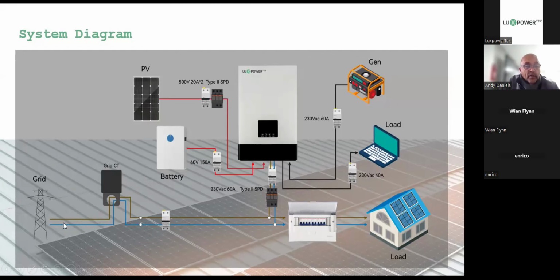So it'll be on the positive, on the live incoming before the main breaker. There is an arrow on the CT which shows the direction of flow of current, right? So it's always from the grid to the load. That's how it should be installed. And if you do make a mistake with that, you can always reverse on the maintenance page. We do give you an option to reverse the direction of the CT if you've installed it incorrectly.